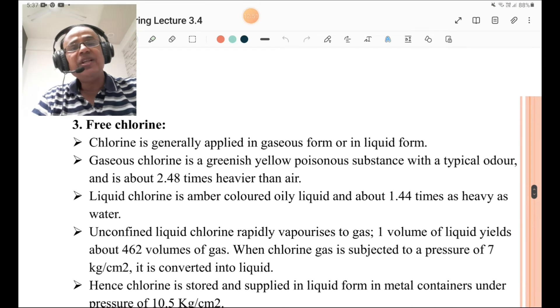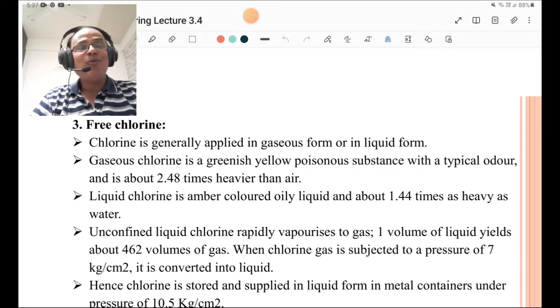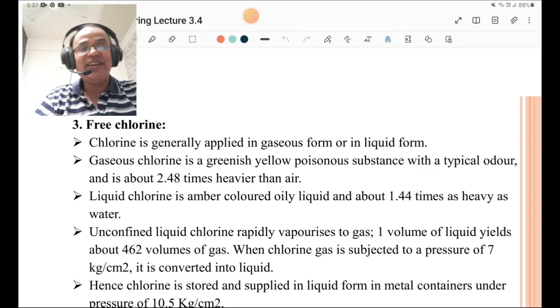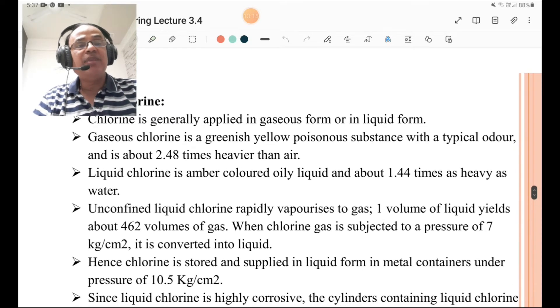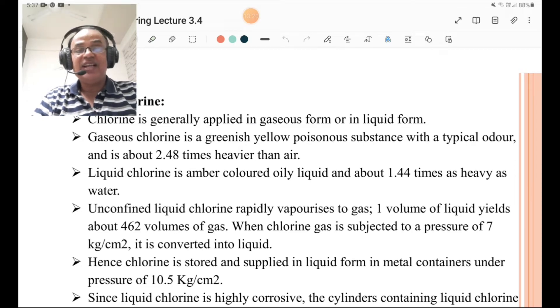Free chlorine: chlorine is generally applied in gaseous or liquid form. Gaseous chlorine is a greenish-yellow poisonous substance with a typical odor and about 2.48 times heavier than air — you must remember that. Liquid chlorine is an amber-colored oily liquid and about 1.44 times as heavy as water.